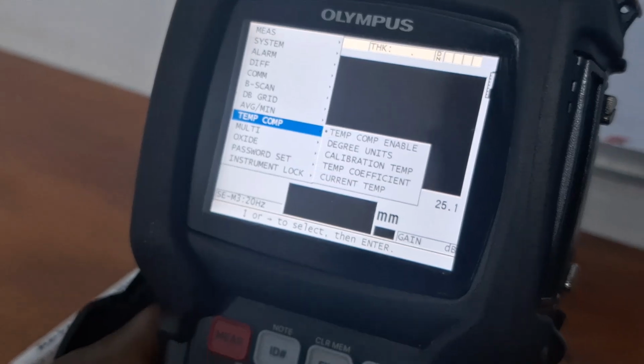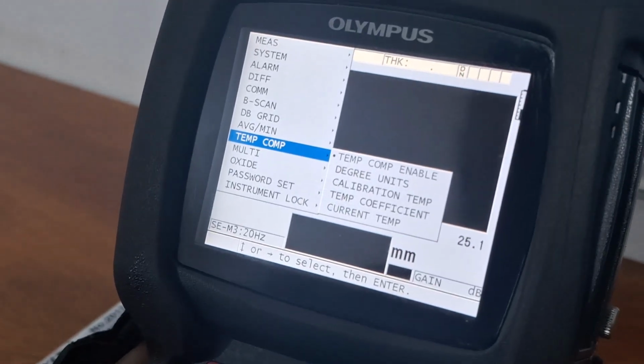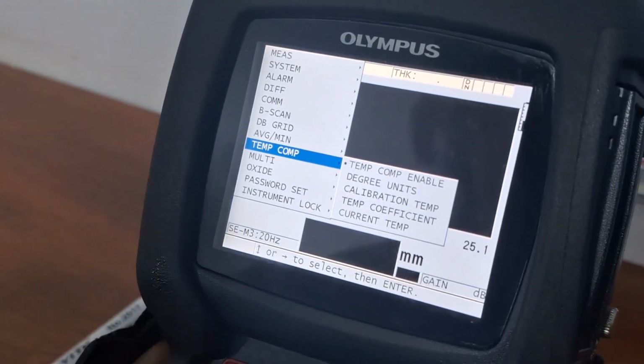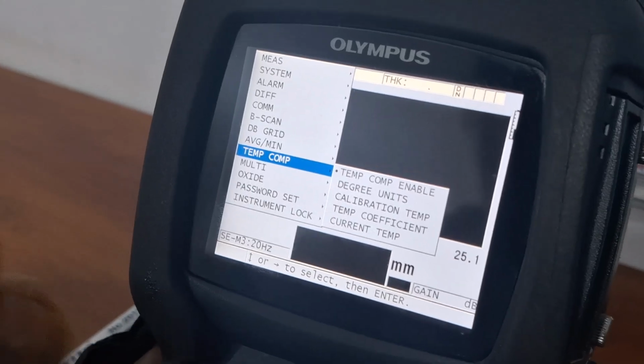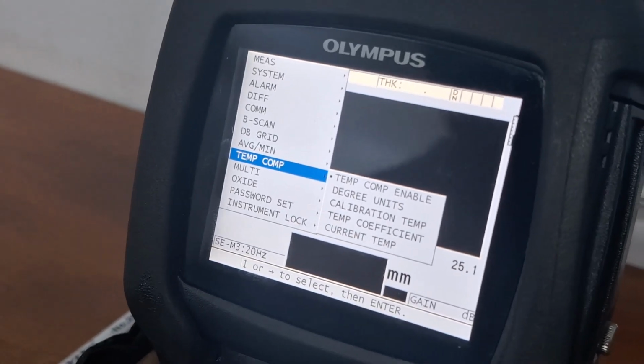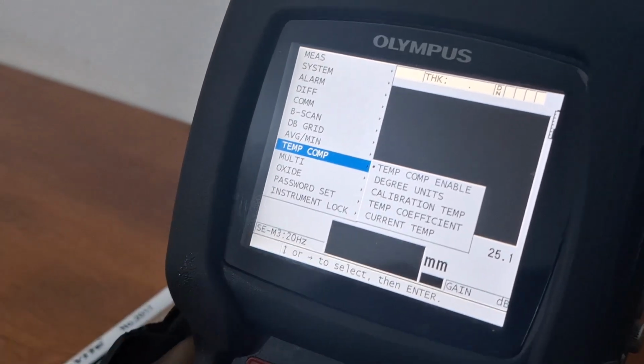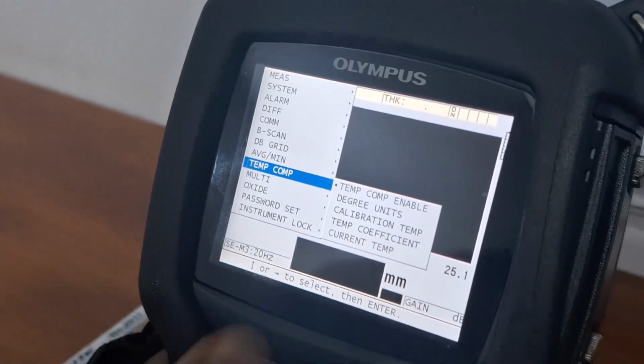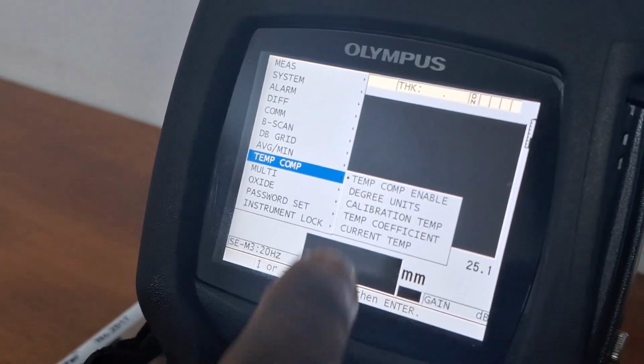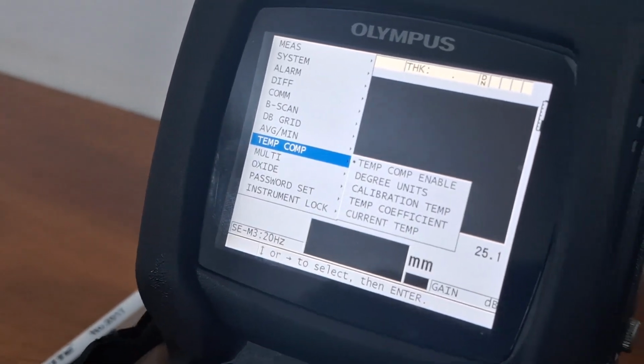Now, I want you to also have this at the back of your mind. Your material you are calibrating with your calibration block, it's at room temperature. The material you are testing is at a different temperature. So definitely there will be a temperature change which will be reflected in what we call your temperature coefficient. In this case, the machine automatically does the calculation.